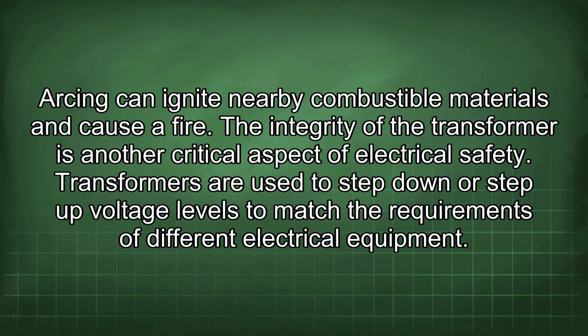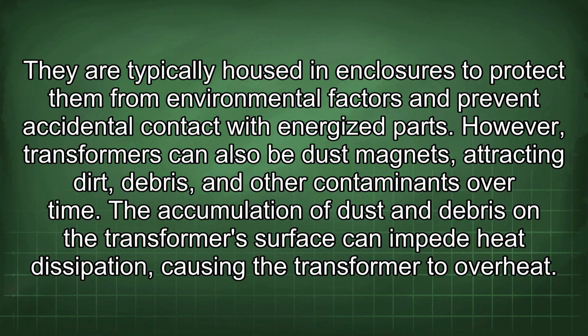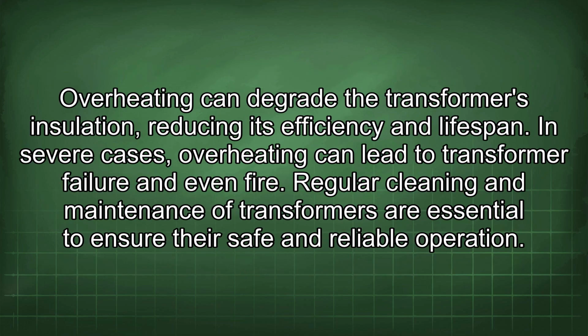The integrity of the transformer is another critical aspect of electrical safety. Transformers are used to step down or step up voltage levels to match the requirements of different electrical equipment. They are typically housed in enclosures to protect them from environmental factors and prevent accidental contact with energized parts. However, transformers can also be dust magnets, attracting dirt, debris, and other contaminants over time. The accumulation of dust and debris on the transformer's surface can impede heat dissipation, causing the transformer to overheat. Overheating can degrade the transformer's insulation, reducing its efficiency and lifespan.